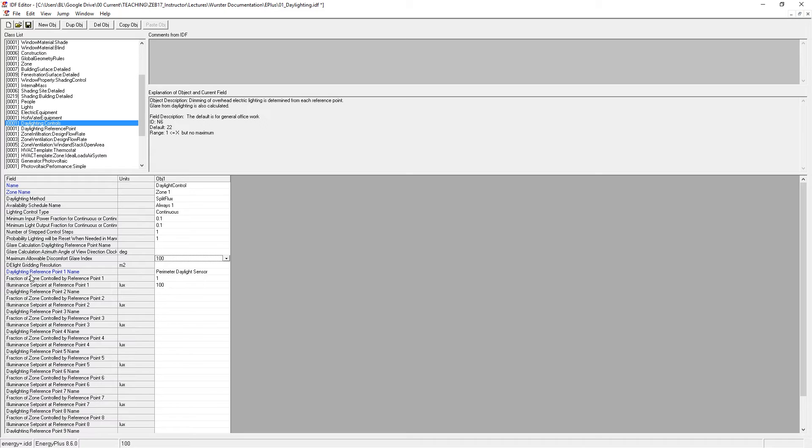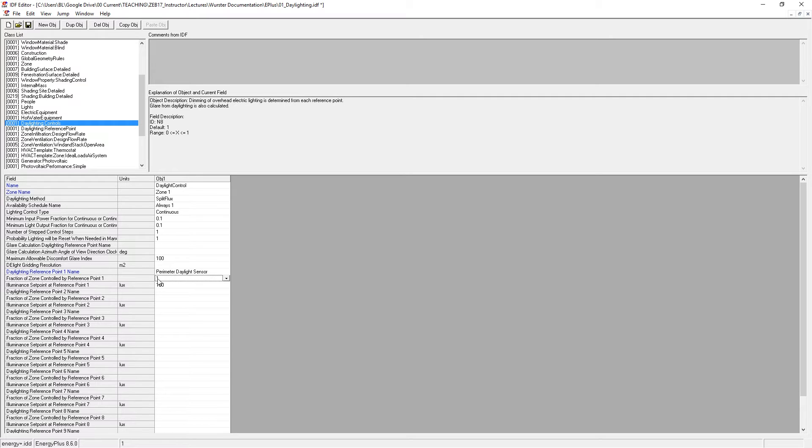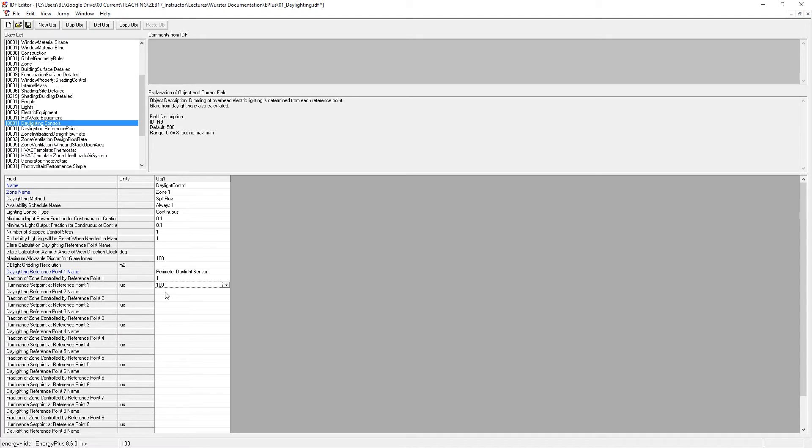And then finally, the daylight reference point, which is our sensor. And these two very important parameters. One, this one, is the fraction of the zone controlled by that point. So right now it's set to 100%. And the second is the illuminance set point at that point. So in this case, I'm setting this to 100 lux, which is a good rule of thumb. Usually either 100 lux or 300 lux is an appropriate set point for rudimentary calculations.